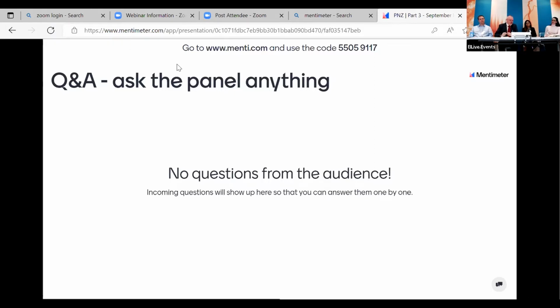In that specific example, I think the feeling is that that's not a satisfactory solution in even the medium term. It's a way of stepping around the problem that was immediately observed. But we need to find more fundamental ways of modeling the stability of the system and gaining assurance of it. And it's problematic because the manufacturers are not able to do a full disclosure of what the software does. They may give a black box model, that is, they compile some computer code that will replicate the behaviors and put an input in and observe an output within the system model. But it's not letting you understand what the phenomena are underlying the instability.